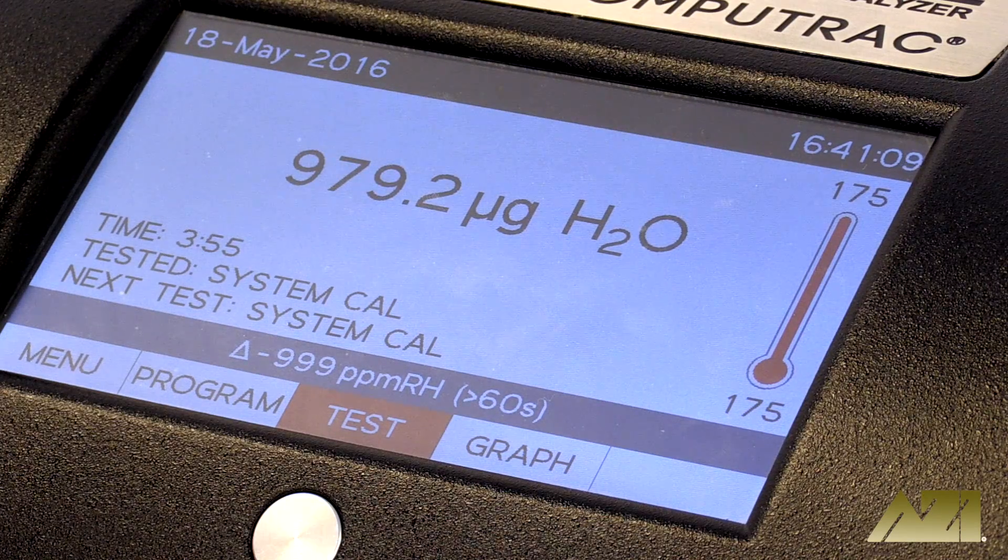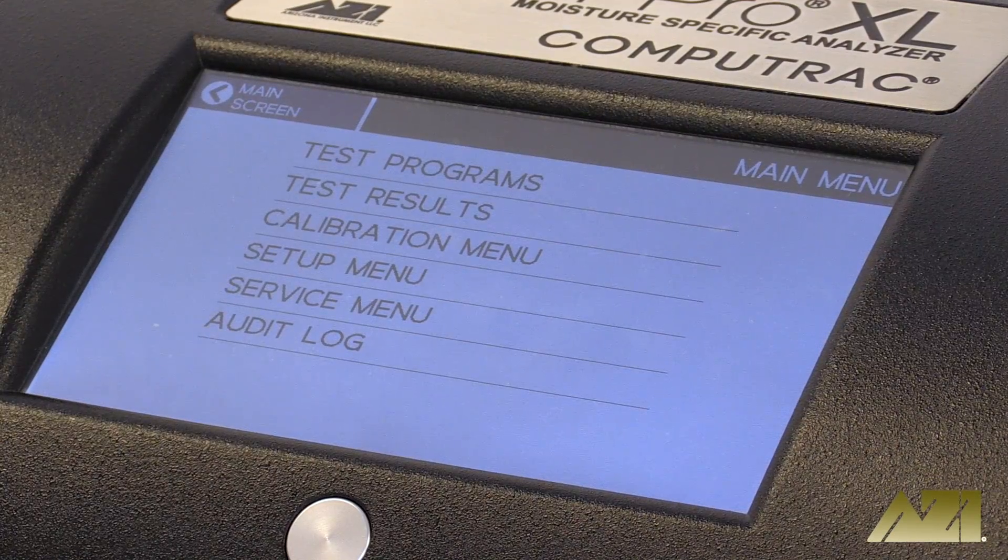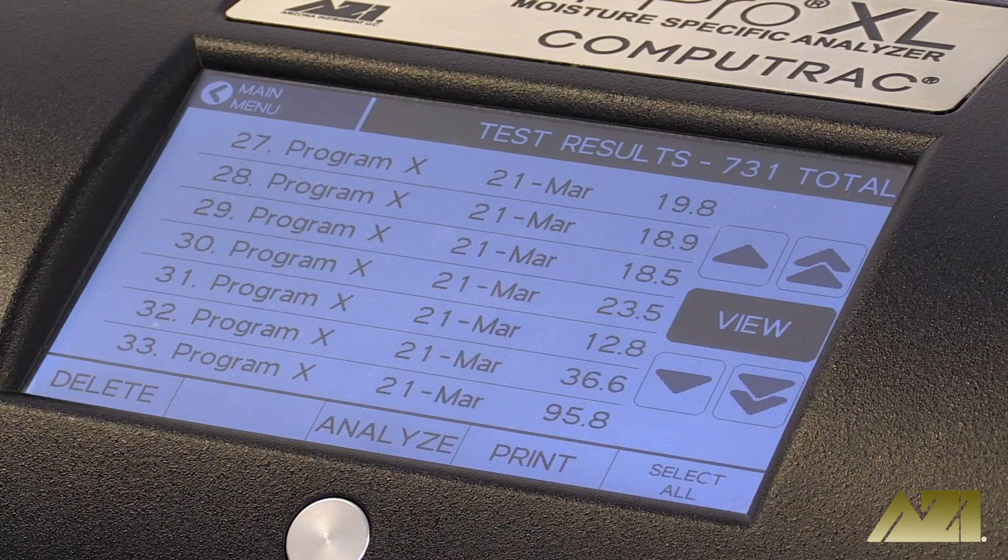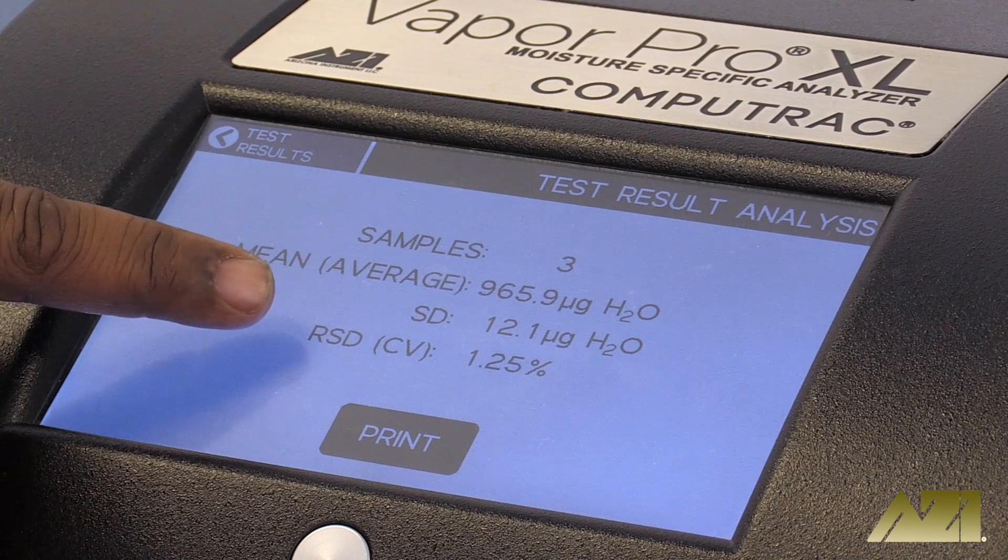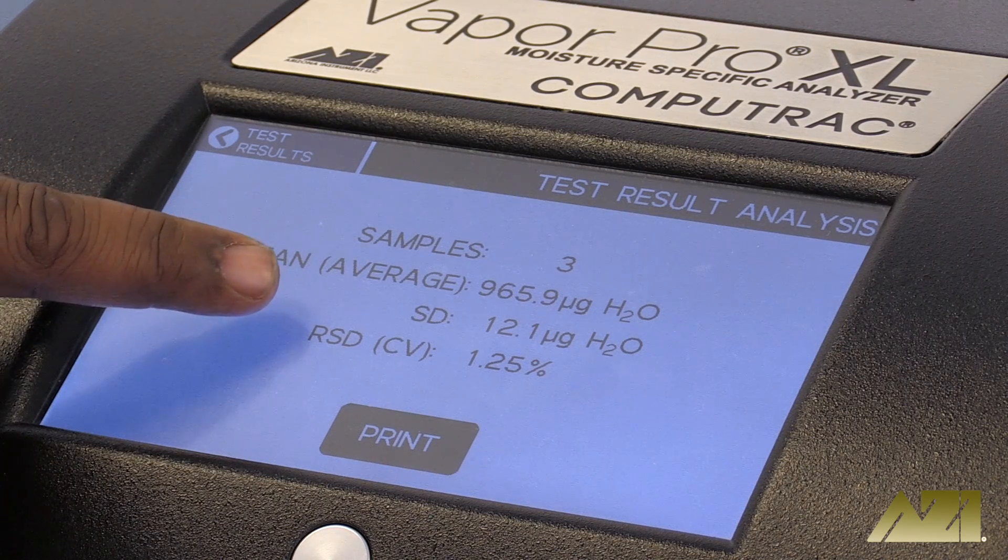Follow the on-screen prompts to perform the analysis. If the standard deviation is less than 50 and the coefficient of variation is less than 5, the instrument does not need to be recalibrated.